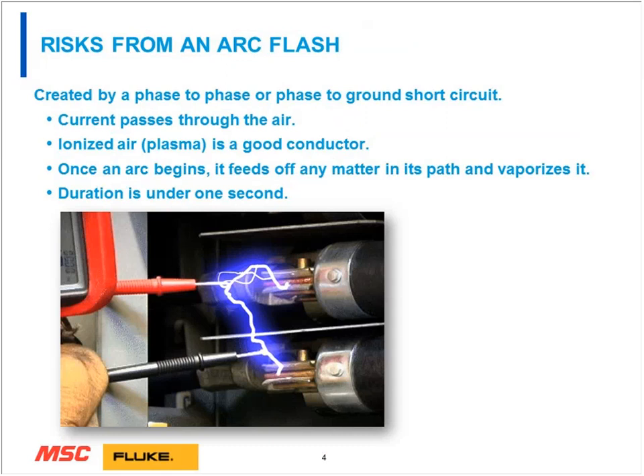There are some risks from an arc flash. Now, the arc flash is created from a phase-to-phase or a phase-to-ground short circuit. Current passes through the air, and I like to equate it to almost what we call a Jacob's ladder effect. That's from the old Frankenstein movies where you've seen the arc of voltage jump between two different V-shaped probes as it rises. Ionized air starts to heat, the arc travels upward until its resistance gets so high that it extinguishes itself, and starts again at the bottom. And that's really what happens in an arc flash incident.